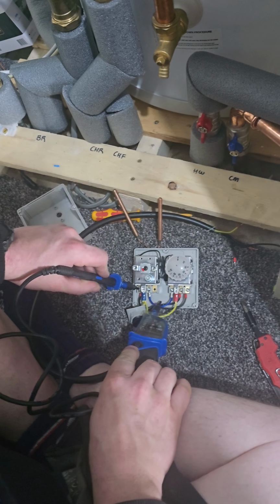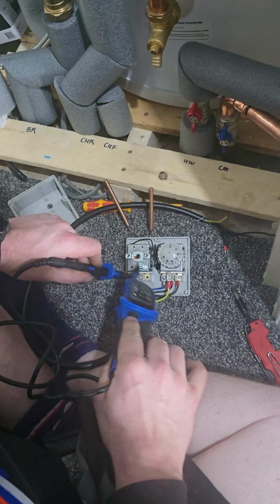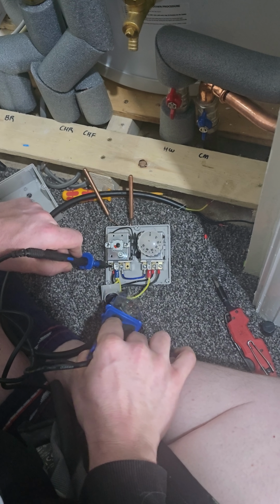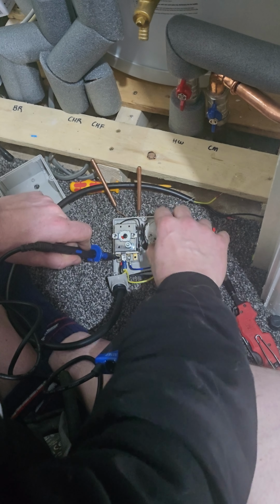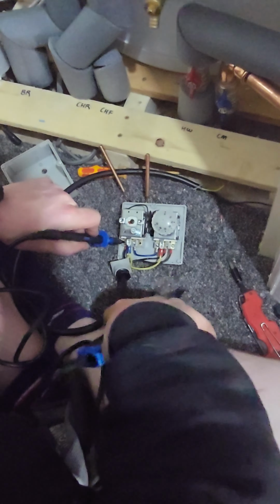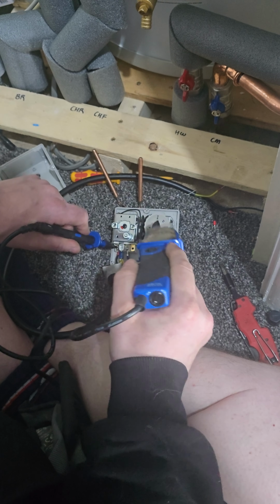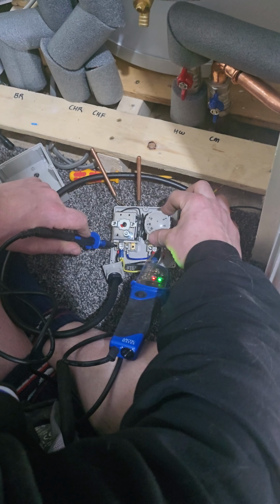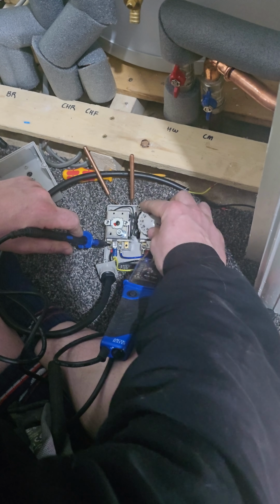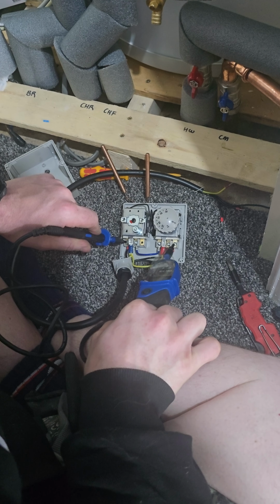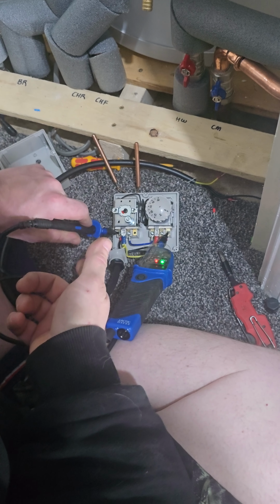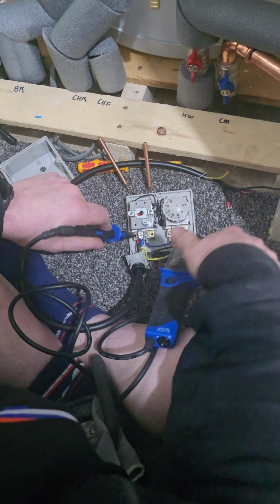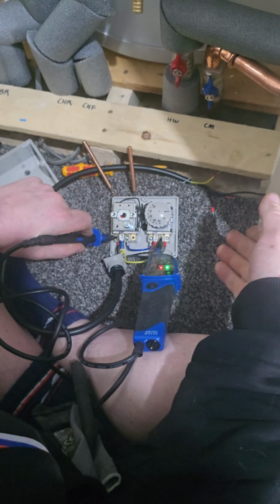Okay, so it's coming out this blue one, which then sends that power like a flow. So this valve's open through into the flow of this one. So this becomes our new common on this knob here. Now we're on 0 at the moment, as low as it will go, which means if you're on a Y plan 3-port or a situation where you need hot water off, it will send the current down, hot water off. And then when you have demand for hot water, it stops saying hot water off and then sends the power down, hot water on here, which then will send power down the switch live to the brown on the zone valve, which will open the zone valve until it's satisfied again. And of course it cuts the power and then sends the power back down to power off.